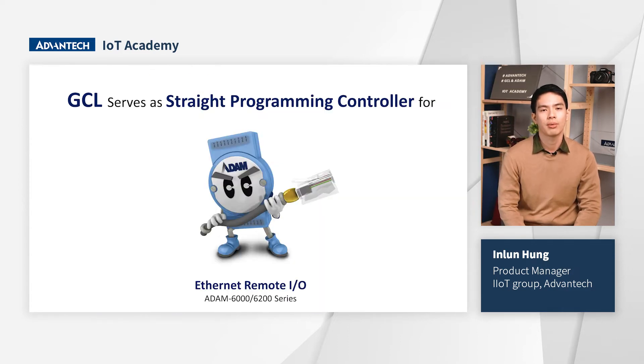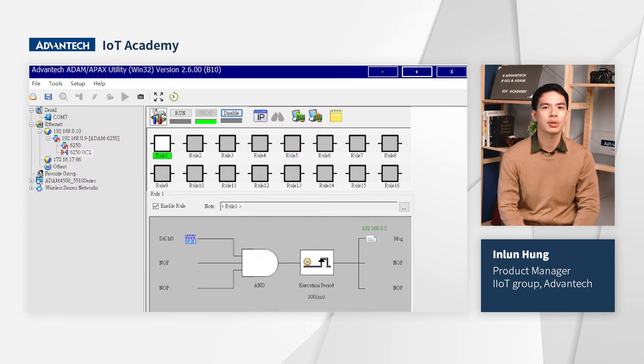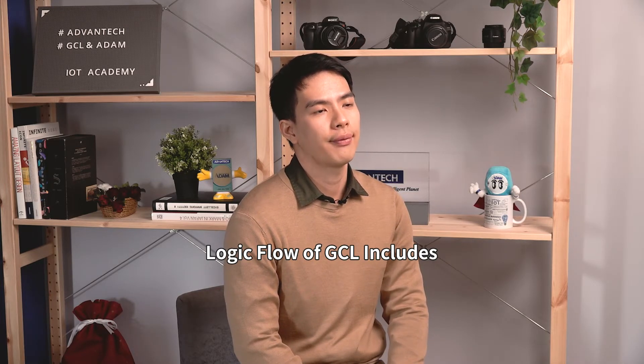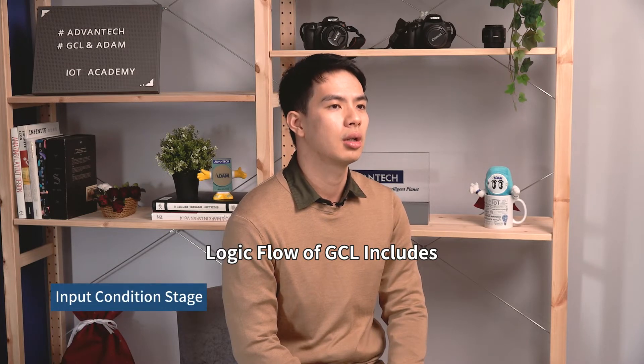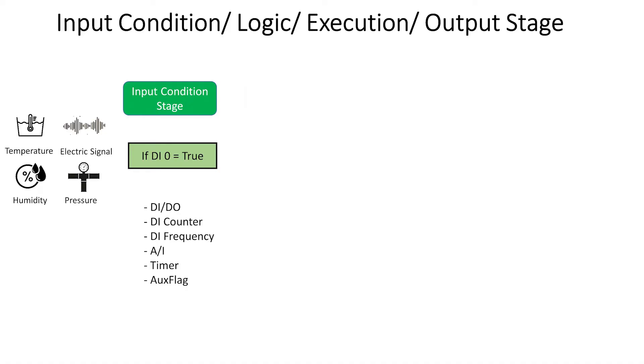GCL serves as a straightforward programming controller in Advantech Ethernet Remote I/O, ADAM 6000 and 6200 series. A key feature of GCL is that everyone can use it — you don't need to write code. With a simple setting, you can control the I/O module, and with the graphic user interface, it is easy to check the flow. The graphic flow in GCL is composed of four stages: input condition stage, logic stage, execution stage, and output stage. The input condition means a logic condition decision based on input data — it can be logic true or false.